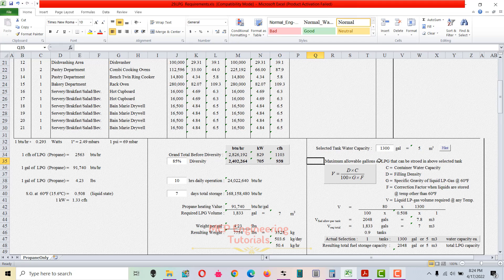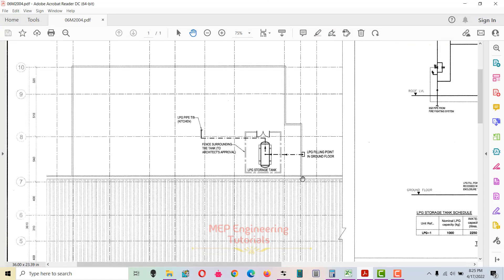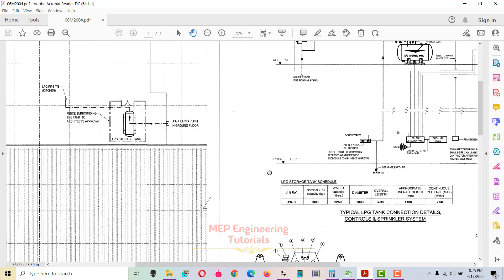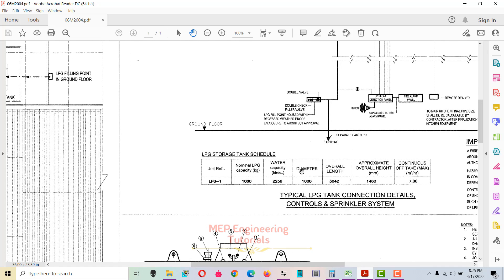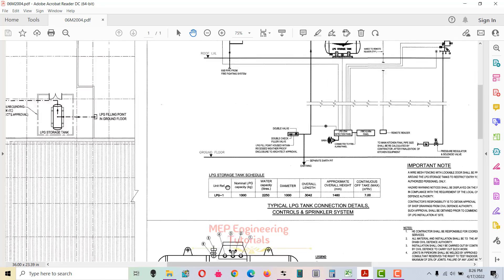Now we need to select the tank water capacity. LPG tanks are specified in water capacity form — water capacity represents the size of the tank as if it were filled with water. For example, an LPG tank with a nominal LPG capacity of 1,000 kg has a water capacity of 2,250 liters, as shown in the tank schedule on the drawing.